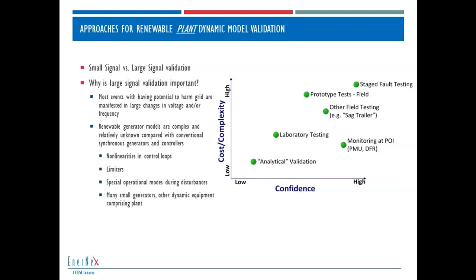The graph there is something I made up several years ago about how we might validate plant testing. We don't do staged fault testing, so in my opinion, monitoring at the point of interconnection with an instrument that has event capture at sufficient resolution is maybe the best way to go about this. For PMU data from the point of interconnection, we're talking about capturing first principle quantities: voltage and the grid current injection. Real and reactive power are a little bit annoying because it's really the grid current injection that is happening in the model, and that's what we need to validate against.